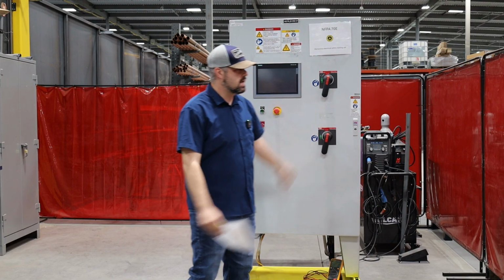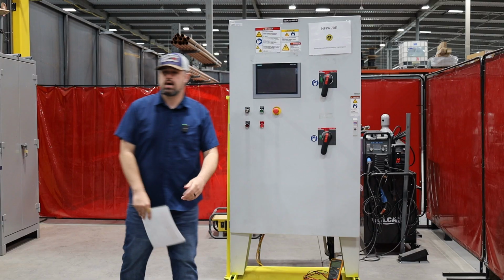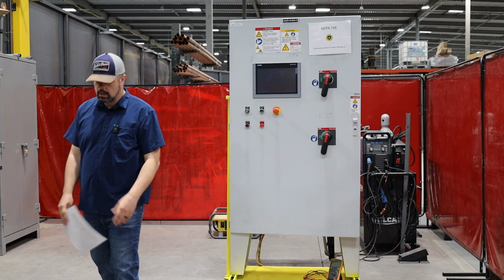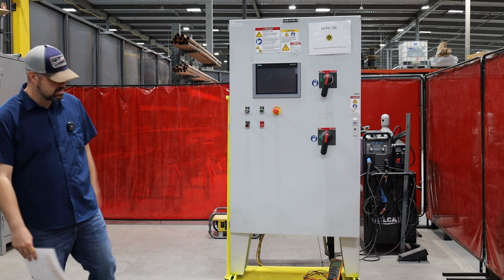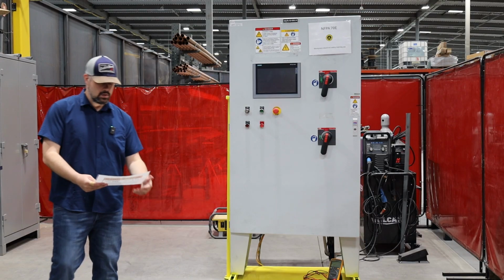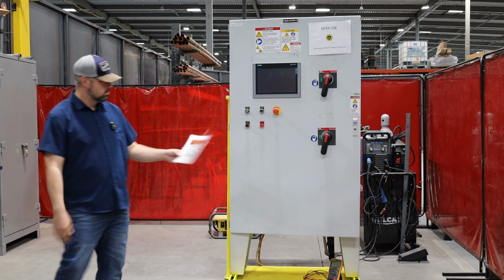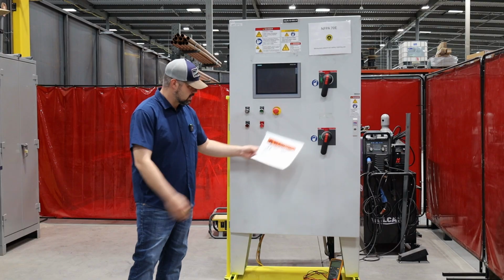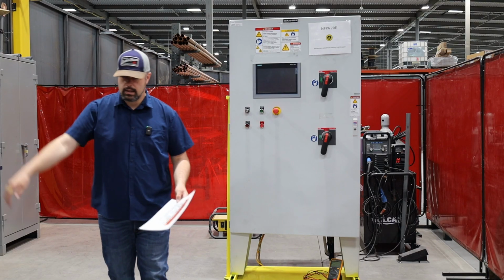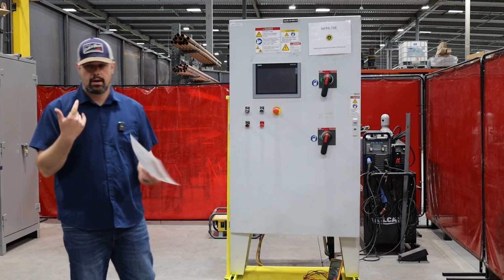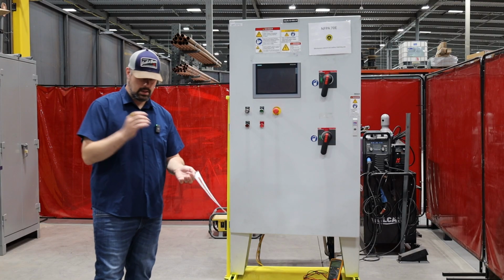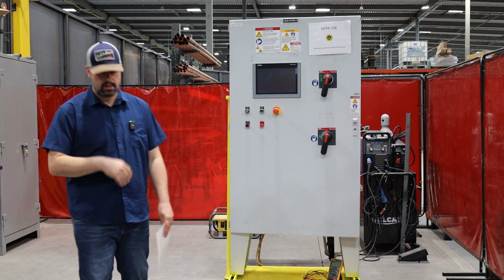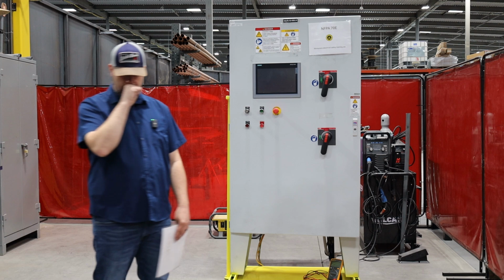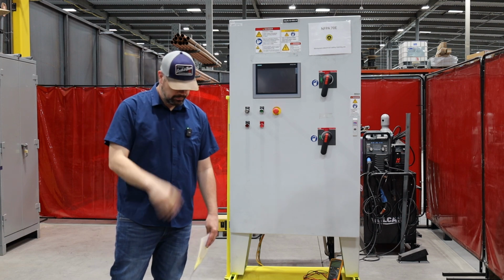I'll say I need you to open this cabinet and just visually check if there's a tripped breaker, or I need you to perform a live-dead-live on the disconnect. I'll give you a scenario, and then you need to walk me through. You need to read every aspect of this label and say, okay, I'm going to have my boundary here. I'm going to need to wear this PPE, and I need you to be specific, right?